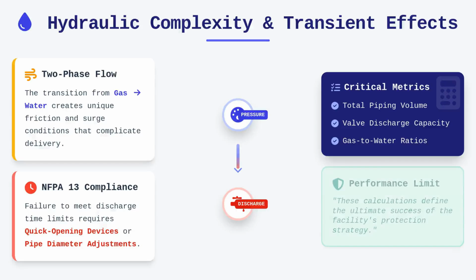These calculations are not merely academic. They define the performance limit of the protection strategy for the facility. Always evaluate the gas-to-water pressure ratios during your design phase to ensure the valve will actuate correctly under the specific supply constraints of the site.